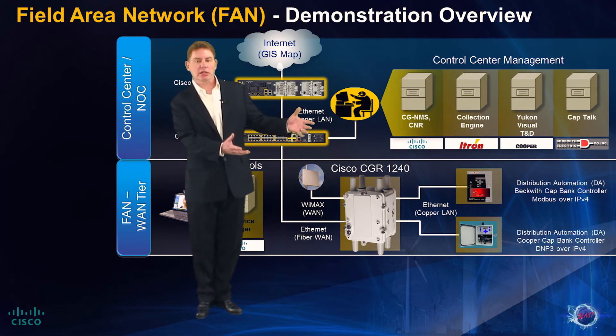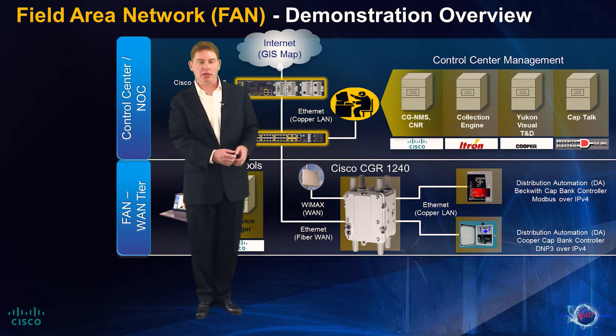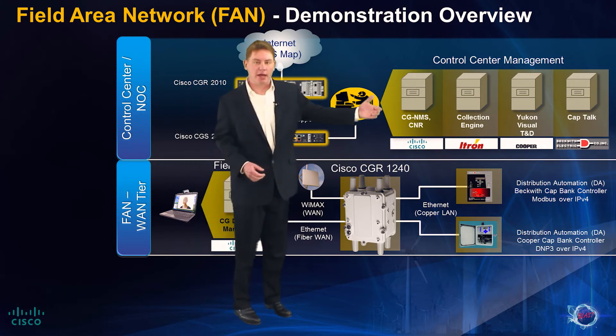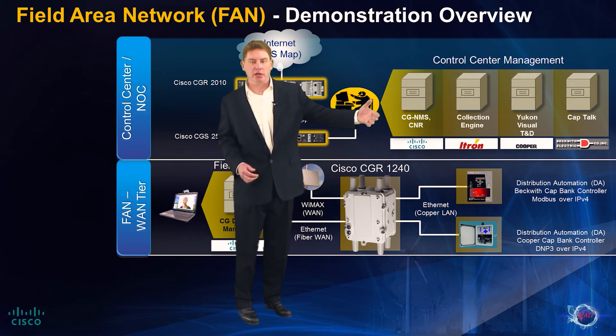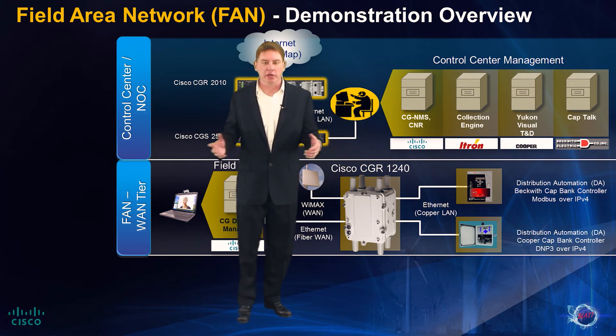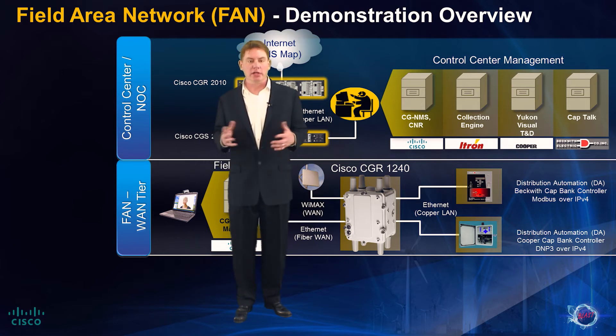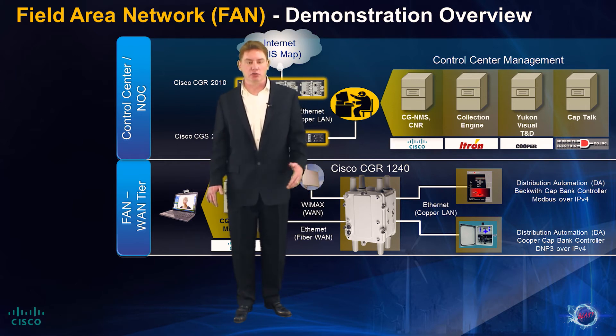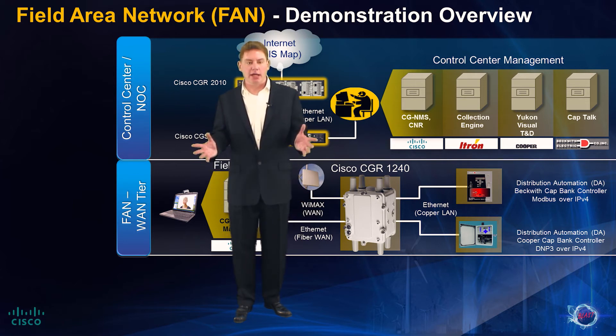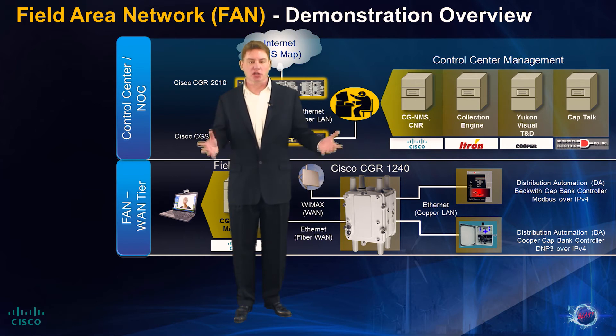The CGR1240 has Ethernet and serial ports that can be used to connect additional devices in the field, like capacitor bank controllers. In this demo, we have two cap bank controllers from partners Beckwith Electric and Cooper Power, connected via Ethernet running either Modbus or DNP3 over IP. This allows the utility to receive data from and control these devices through applications like Yukon Visual T&D or CapTalk. The cap bank controllers are used to ensure the grid is operating as efficiently as possible as part of an integrated volt-var control system.